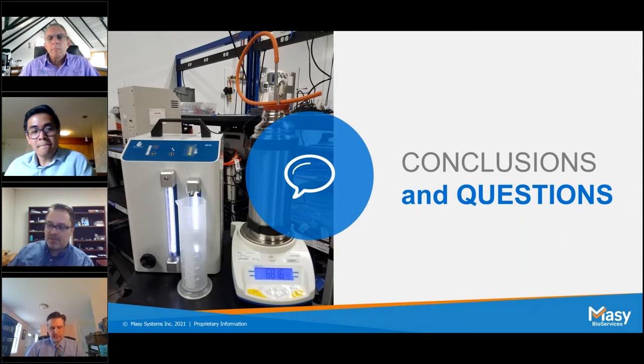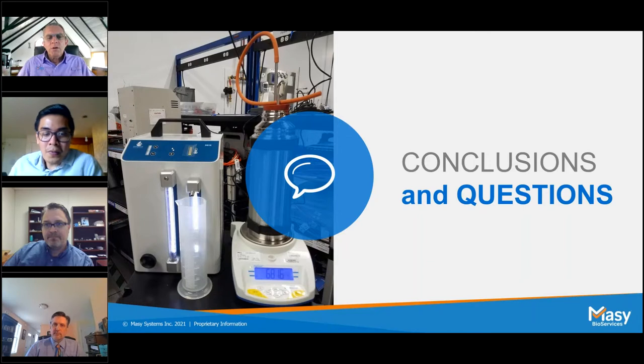You want a cycle that's going to be sufficient for your worst case load item, which is likely to be the largest volume. But again, data will tell you for sure. You don't have to guess. So you'd want to use your development runs to determine what your time needs to be for exposure to get your sterilization. Right, and to add to that, if you are using a large load and a small load, let's say of water, if you're using a large load and a small load with something that's heat impactful, that's going to be a problem. Because with something like an agar, the smaller item will have burnt and no longer be viable. So that's something you have to consider.